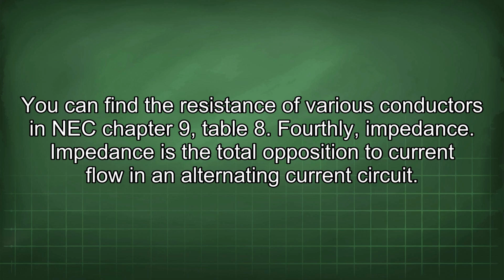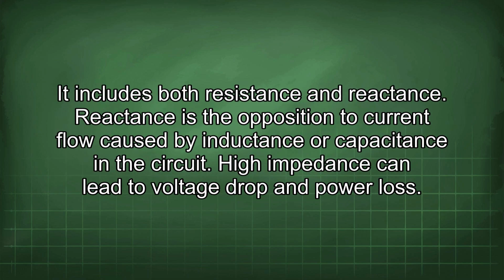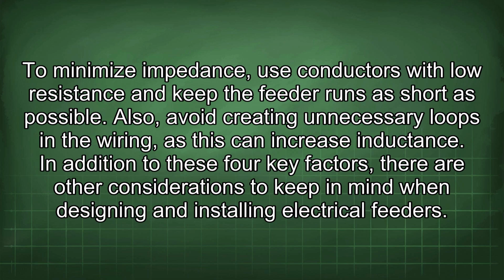Fourthly, impedance. Impedance is the total opposition to current flow in an alternating current circuit. It includes both resistance and reactance. Reactance is the opposition to current flow caused by inductance or capacitance in the circuit. High impedance can lead to voltage drop and power loss. To minimize impedance, use conductors with low resistance and keep the feeder runs as short as possible. Also, avoid creating unnecessary loops in the wiring, as this can increase inductance.